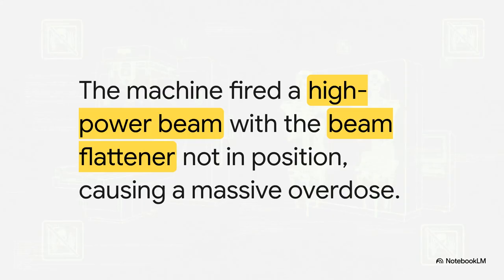And the result of that race? Catastrophe. The turntable stayed in the position for the low-power electron mode, which meant that protective beam flattener wasn't in place. But the machine went ahead and fired the full-power, unfiltered X-ray beam, a concentrated blast of energy about 100 times stronger than intended, directly into the patient.